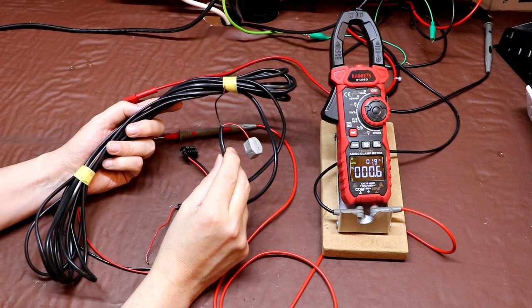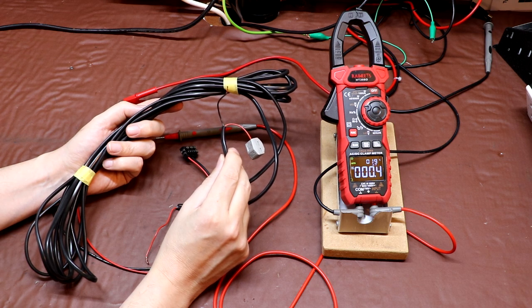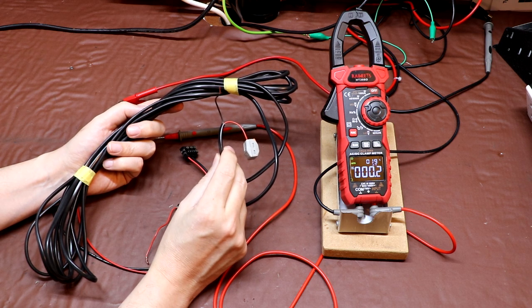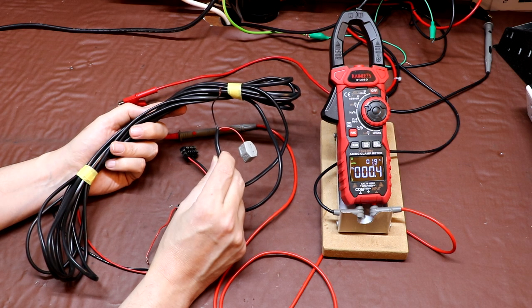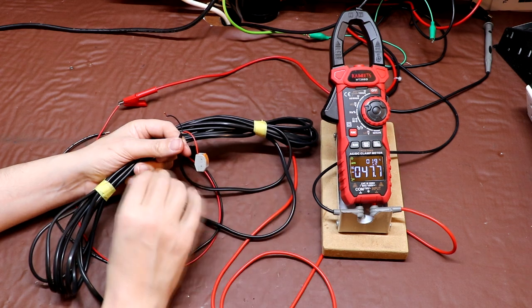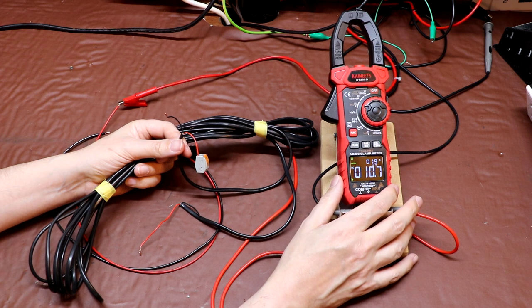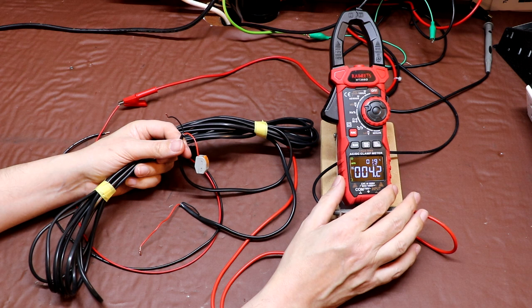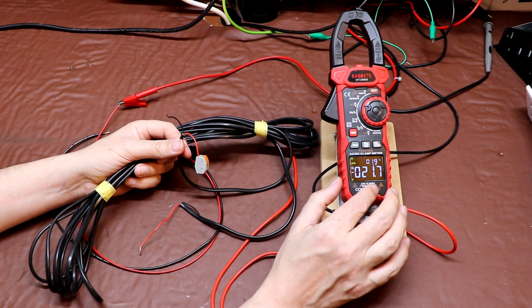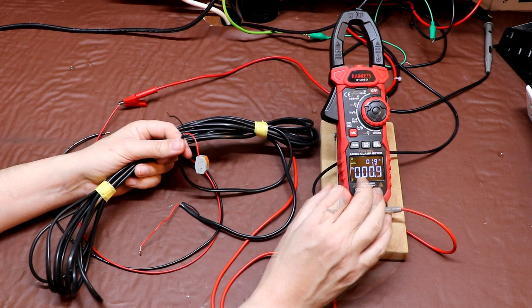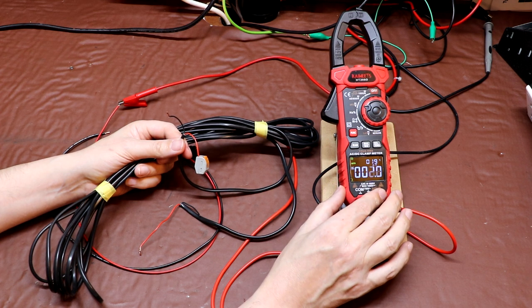So we've just demonstrated there how in an AC circuit the capacitance between one conductor and another can actually lead to induced voltages. In most cases the currents that give rise to those voltages are absolutely tiny. Now, in the case of a modern digital voltmeter like this, because we have such high input impedances, even those very small currents can give rise to quite a significant voltage indication on our meter. Because this effect is caused by stray capacitance within the cabling, it only affects AC and not DC circuits.